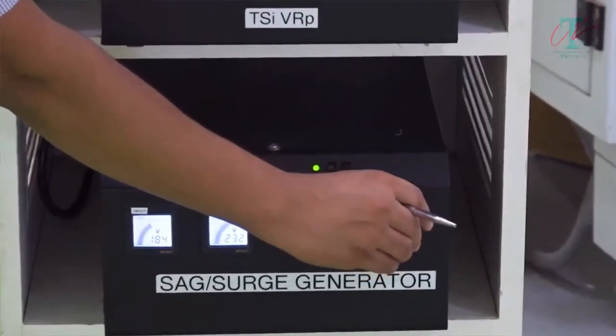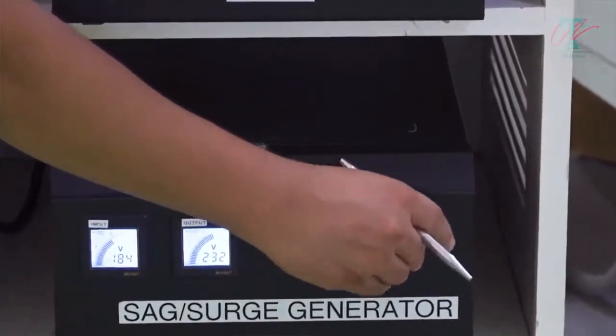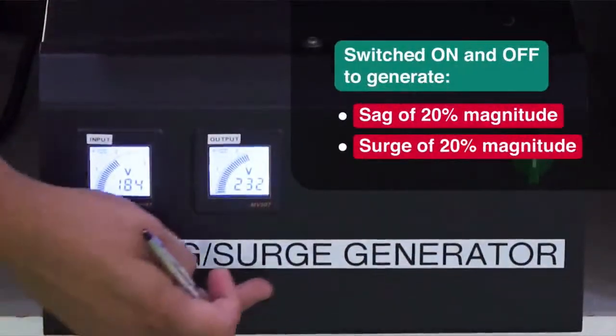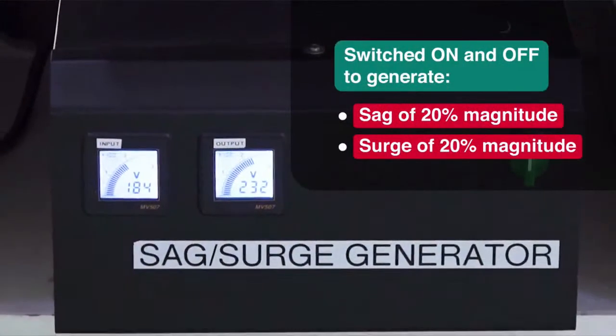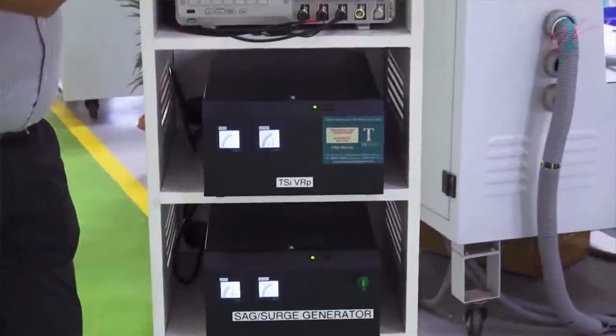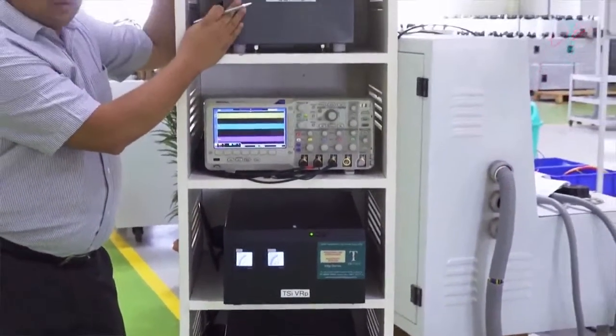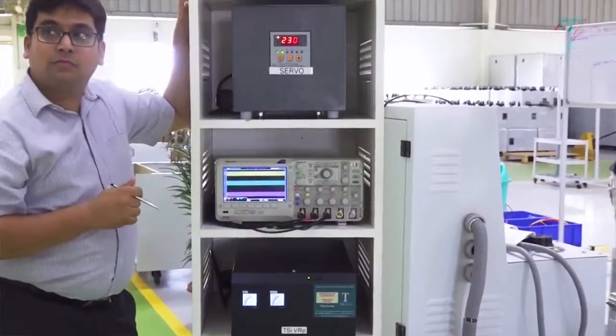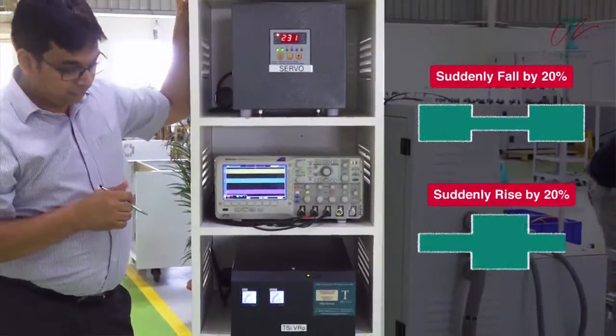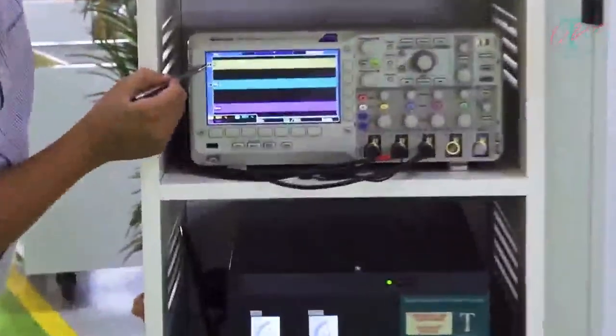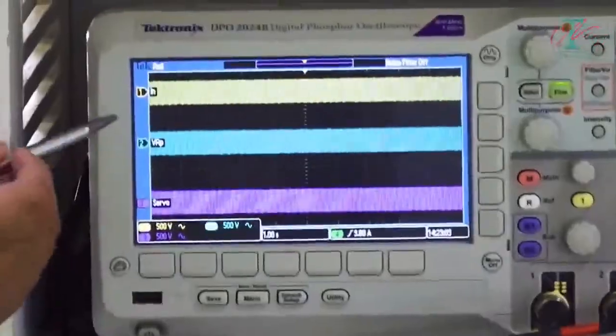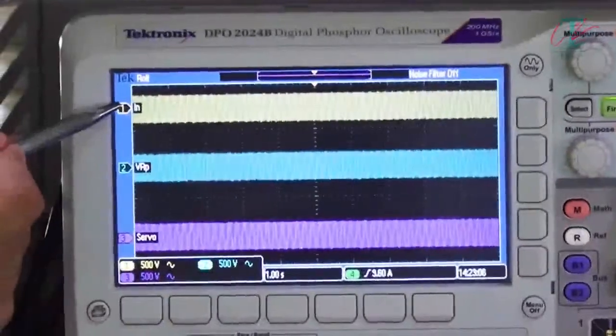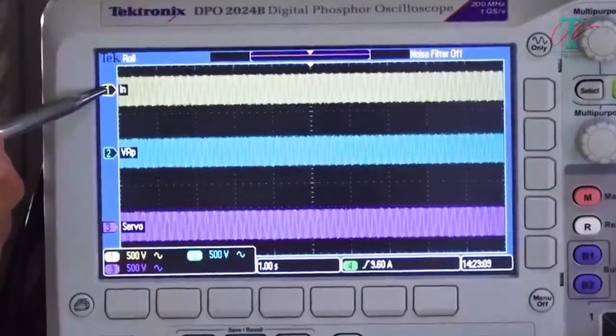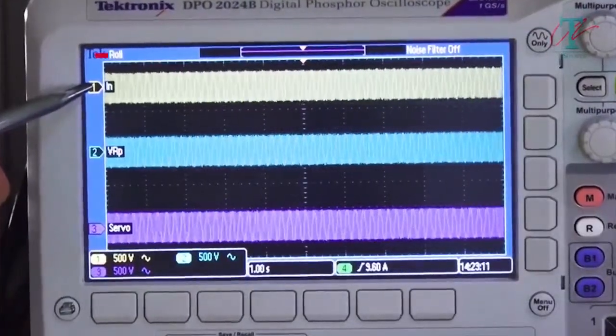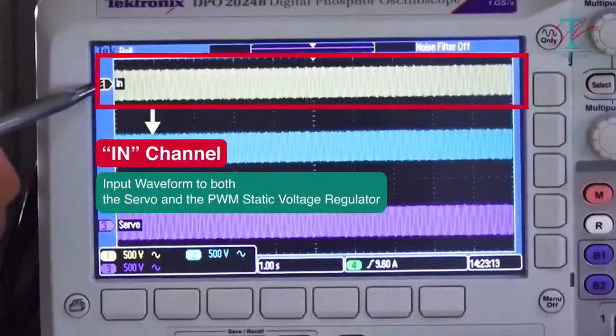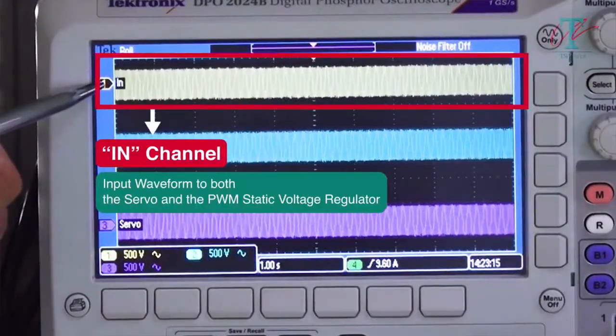The sag surge generator can be switched on and off by this switch to generate either a sag of 20% magnitude or a surge of 20% magnitude. Accordingly, the input voltage to both the static voltage regulator and the servo voltage stabilizer will either suddenly fall by 20% or suddenly rise by 20%. To monitor the resultant performance, there is an oscilloscope with 3 channels. As you can see, this yellow top channel records the voltage waveform generated by the sag surge generator, marked as the input waveform to both the servo and the static voltage regulator.